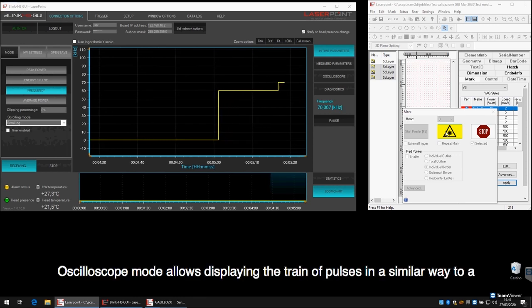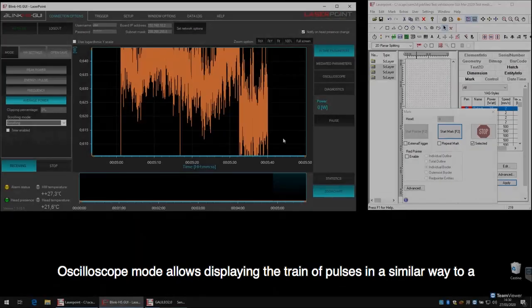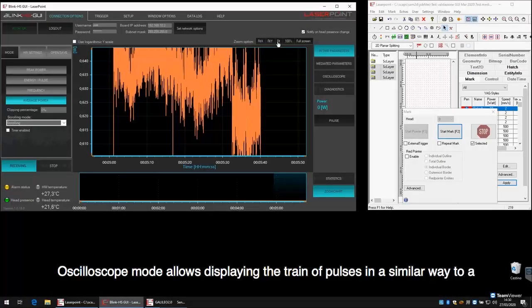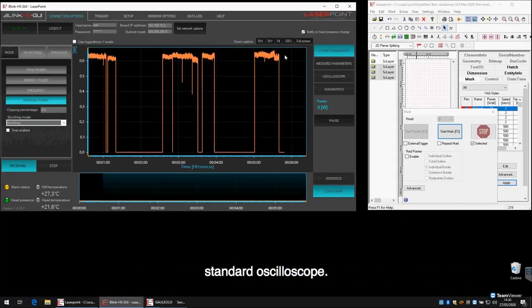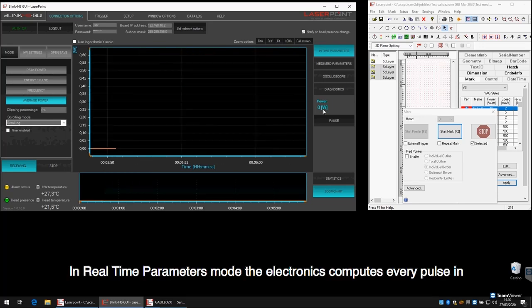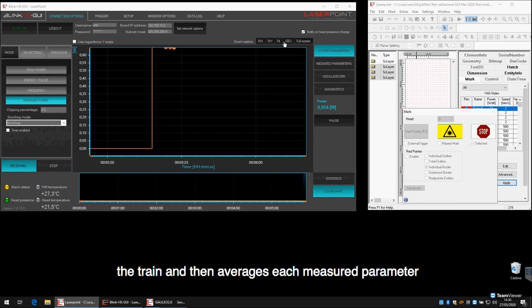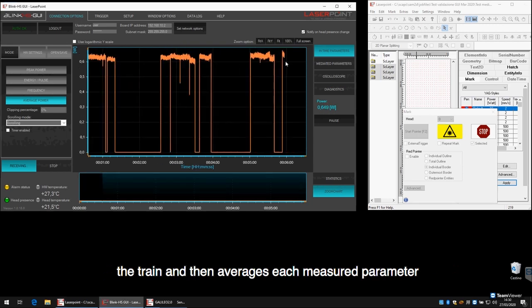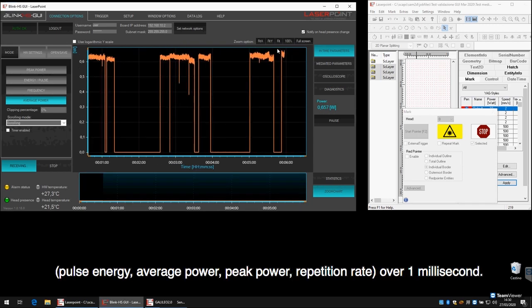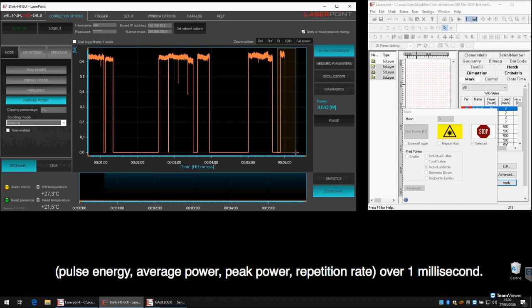Oscilloscope mode allows displaying the train of pulses in a similar way to a standard oscilloscope. In real-time parameters mode, the electronics computes every pulse in the train and then averages each measured parameter: pulse energy, average power, peak power, and repetition rate.